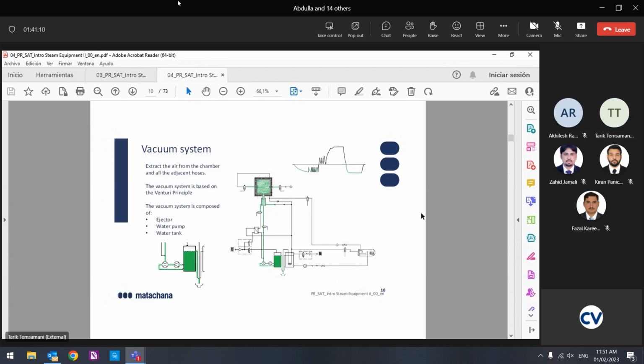So this is the chamber, okay? Vacuum line, the green one. This valve is for the heat exchanger. It's closed. Everything is closed during the vacuum. In the vacuum, only the chamber is under vacuum. So the vacuum is the green line you see in this cycle profile. For the green line, we use this pump and this tank.